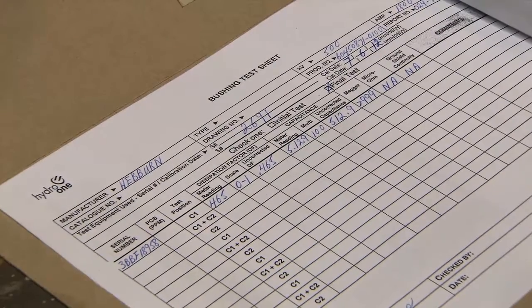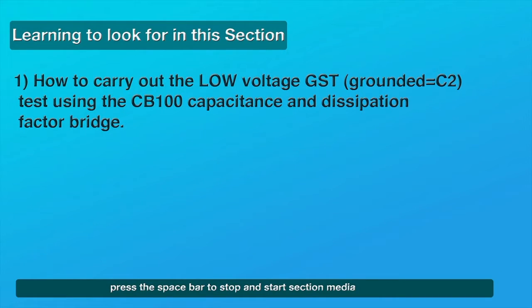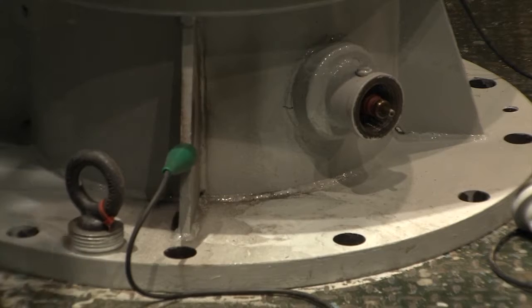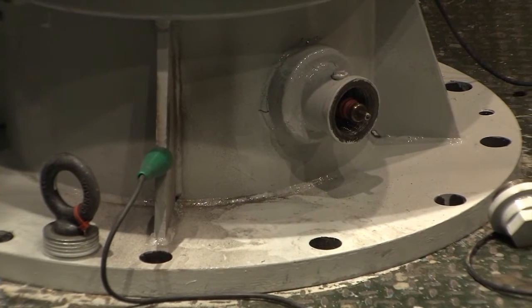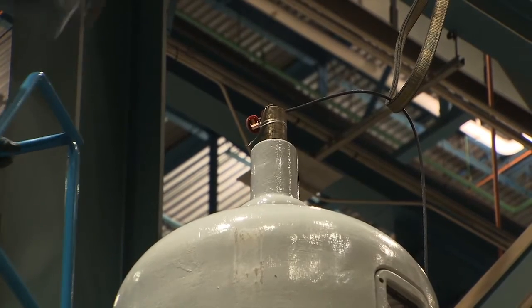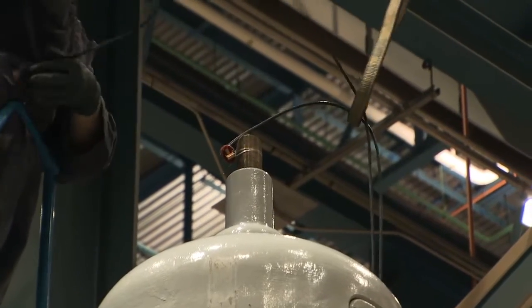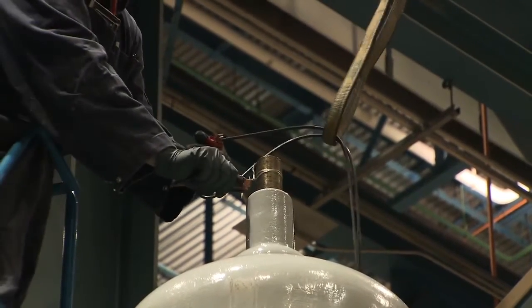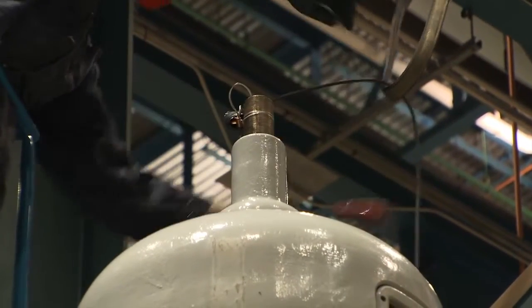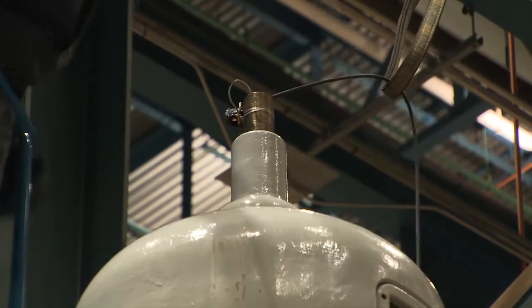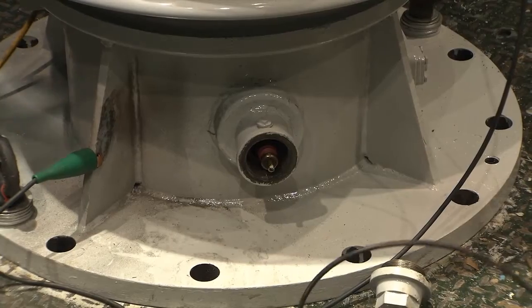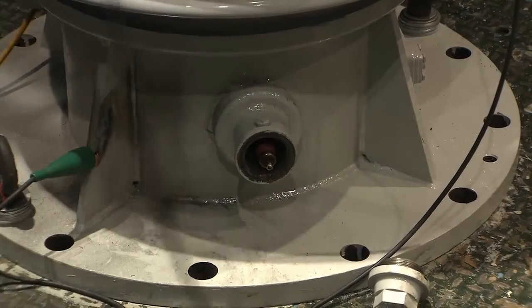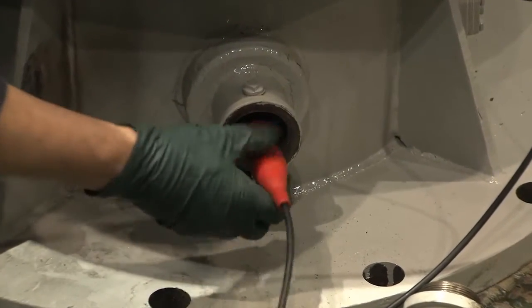When the test has been completed, make the appropriate entries on the bushing test sheet as required. The final low-voltage GST electrical tests for capacitance and dissipation factor. To make the connections for the C1 plus C2 test, begin by removing the low-voltage lead from the capacitance tap. Remove the high-voltage lead from the connection to the bare copper wire on the threaded rod at the top of the terminal and replace it with the low-voltage lead. The cable is still supported through a sling suspended on the hoist hook. Connect the high voltage lead to the capacitance tap on the flange.